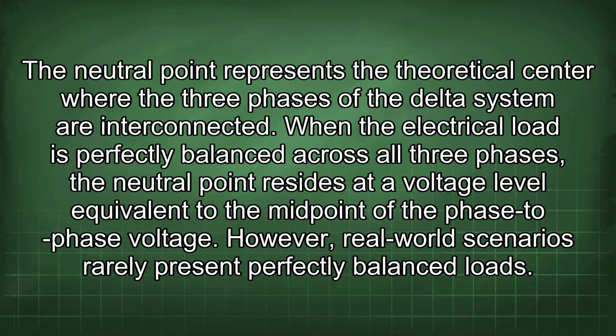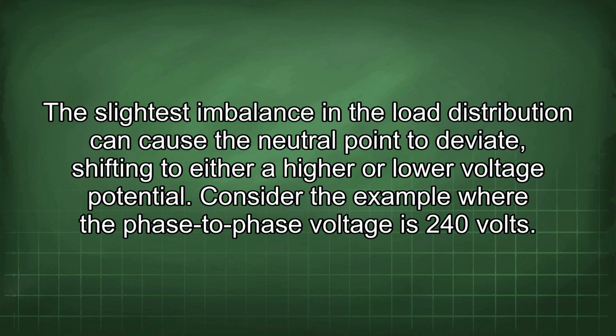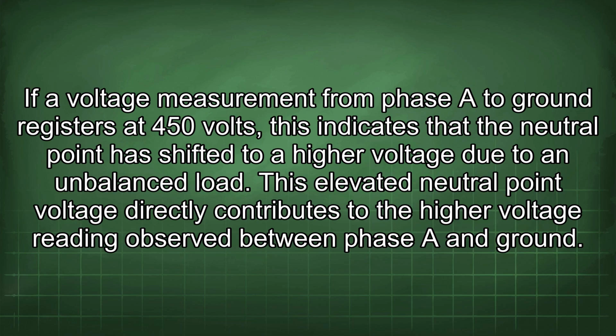However, real-world scenarios rarely present perfectly balanced loads. The slightest imbalance in the load distribution can cause the neutral point to deviate, shifting to either a higher or lower voltage potential. Consider the example where the phase-to-phase voltage is 240 volts. If a voltage measurement from phase to ground registers at 450 volts, this indicates that the neutral point has shifted to a higher voltage due to an imbalanced load. This elevated neutral point voltage directly contributes to the higher voltage reading observed between phase and ground.